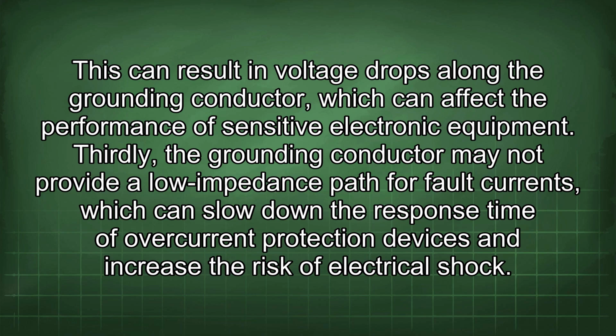Thirdly, the grounding conductor may not provide a low impedance path for fault currents, which can slow down the response time of overcurrent protection devices and increase the risk of electrical shock.